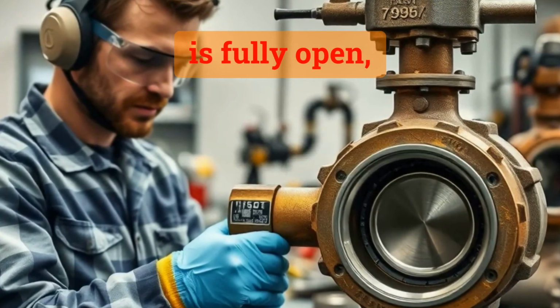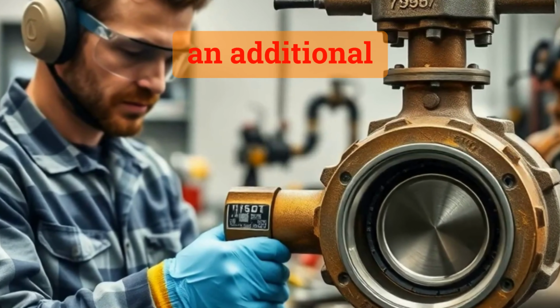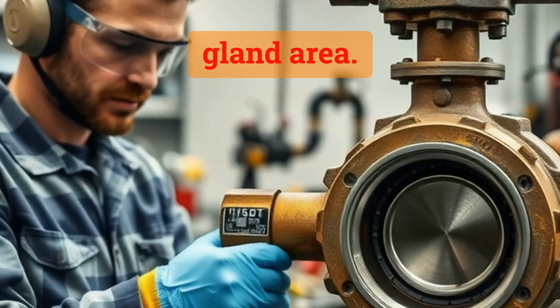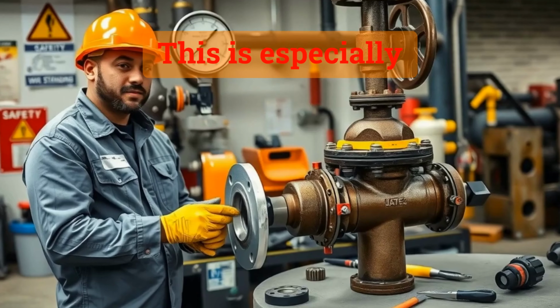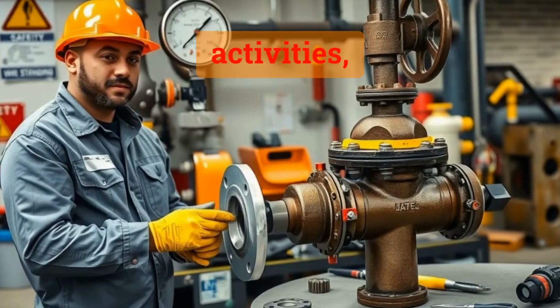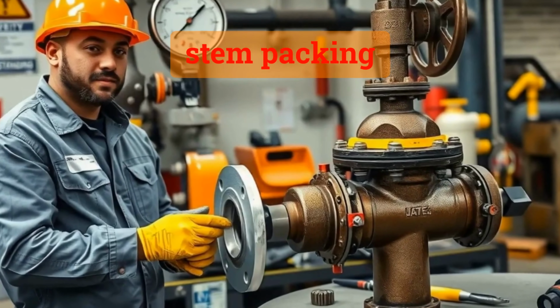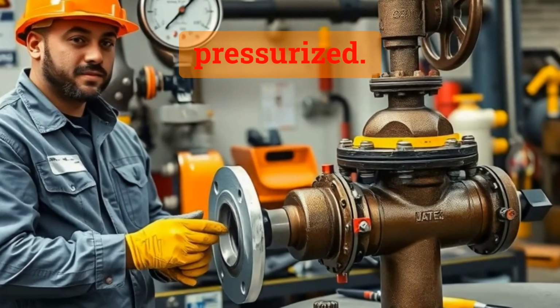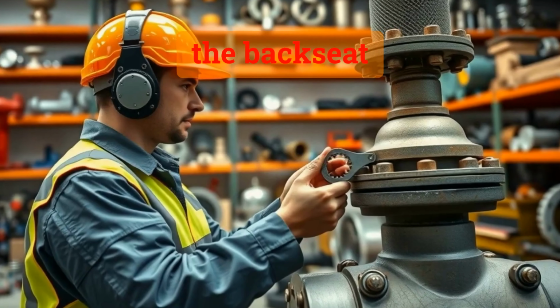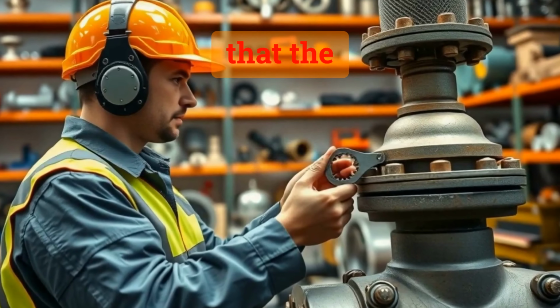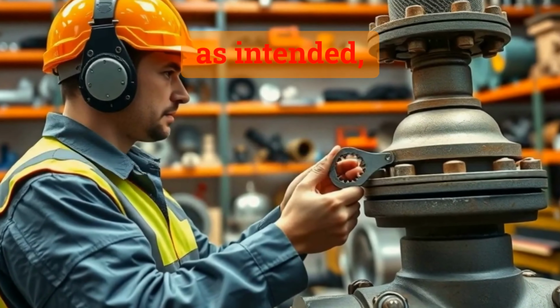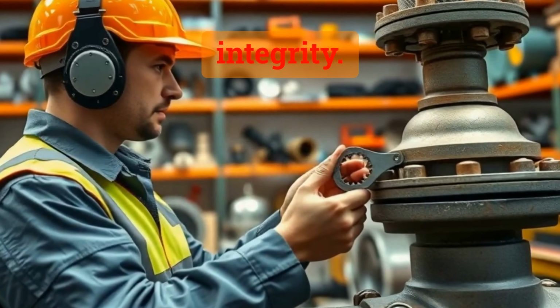When a valve is fully open, the backseat provides an additional seal, preventing leaks from the gland area. This is especially important during maintenance activities, such as replacing stem packing while the system remains pressurized. By performing the backseat test, technicians can confirm that the backseat is functioning as intended, ensuring safety and operational integrity.